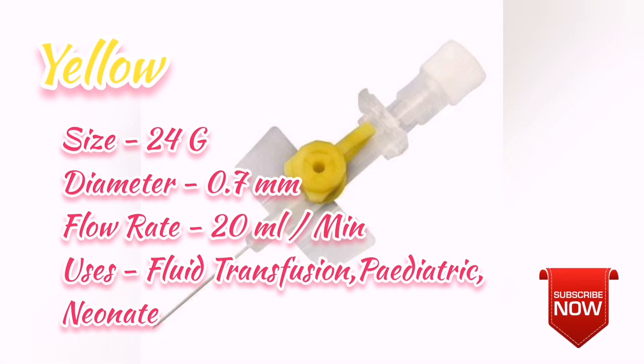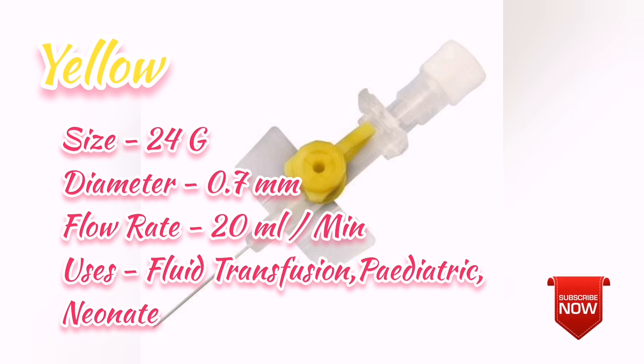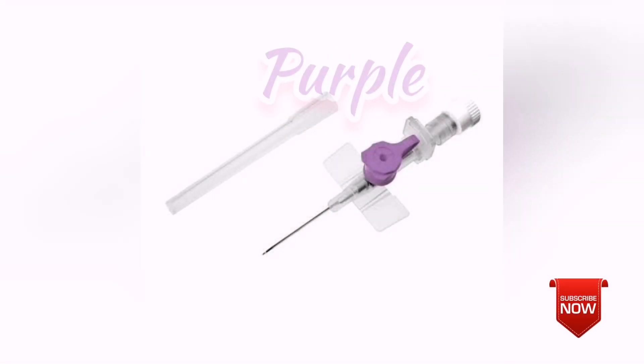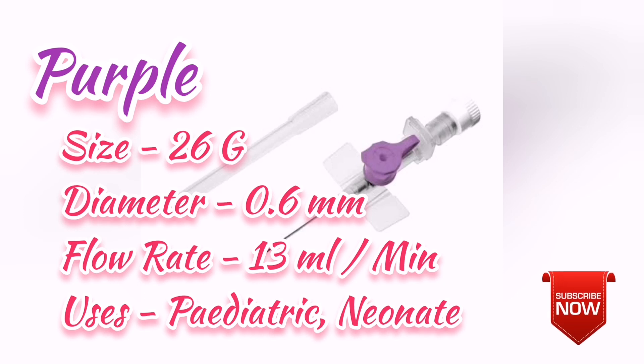The next size is 24G, diameter is 0.7 mm, and flow rate is 20 ml per minute. This is purely pediatric. You can also use this for neonates. If you want to use any color, it will be yellow. The purple color has a size of 26G, diameter is 0.6 mm, and flow rate is 13 ml per minute. This is purely for neonatal purpose.